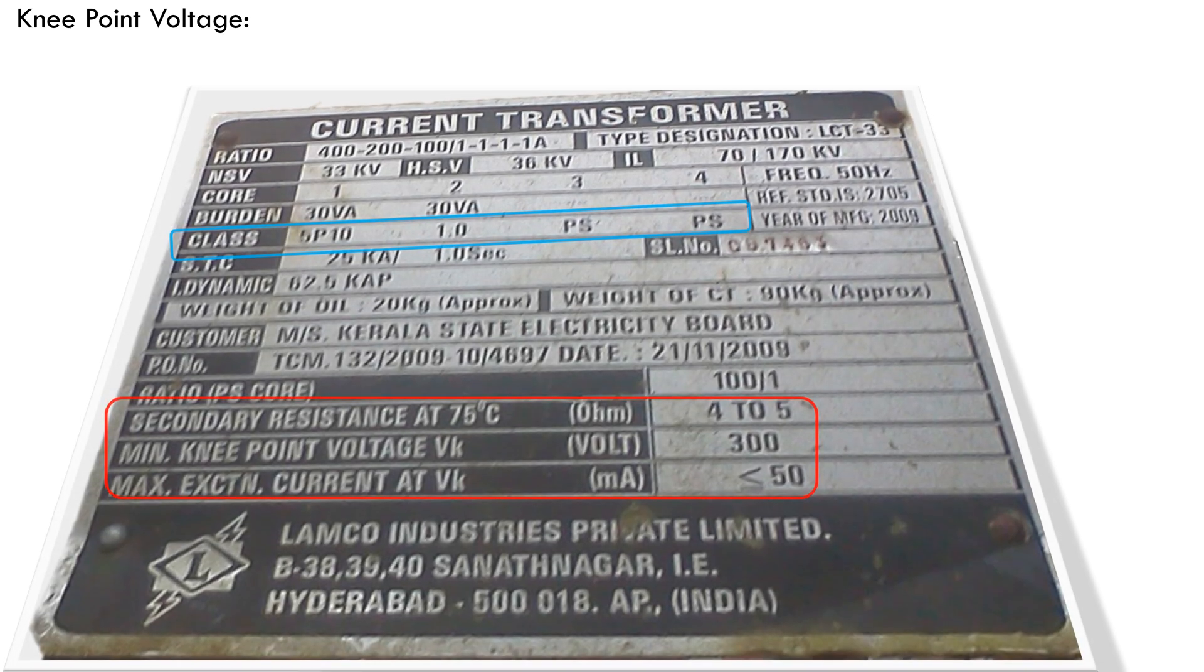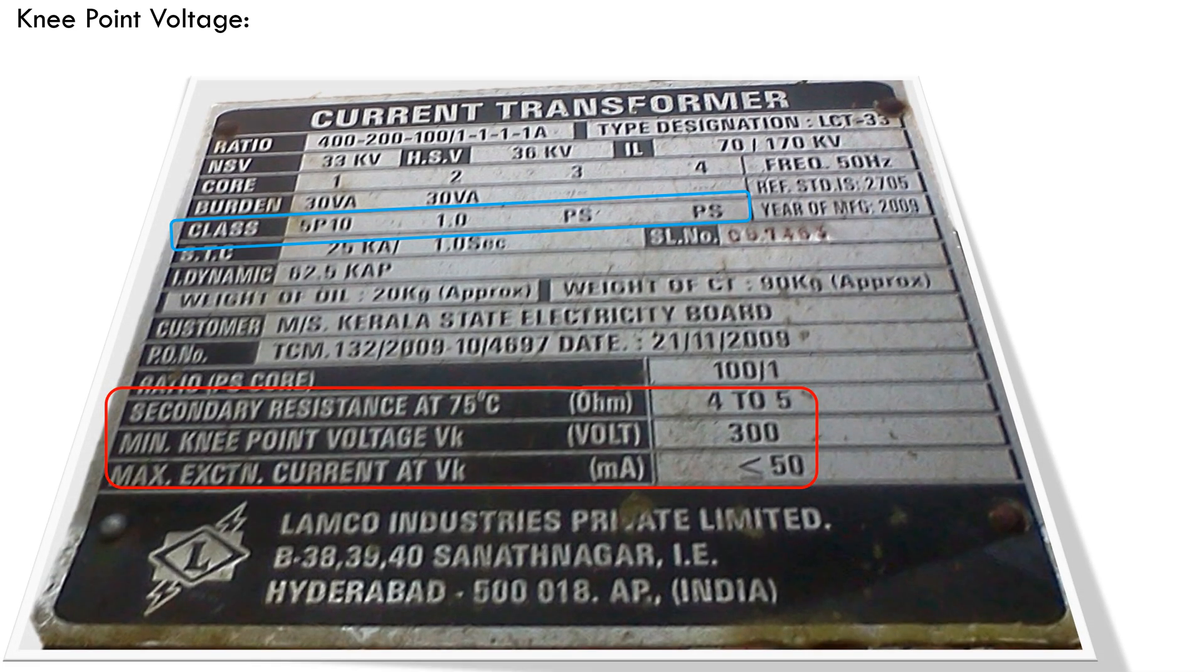Knee point voltage can be obtained from the nameplate details of protection class CTs. However, it is to be verified during commissioning of the new CTs. There are two basic types of CT core, metering core and protection core. The basic difference between these two is for measuring core, the limits are well defined. But, protection cores have to operate over a wide range of currents. So, their characteristics must be different.